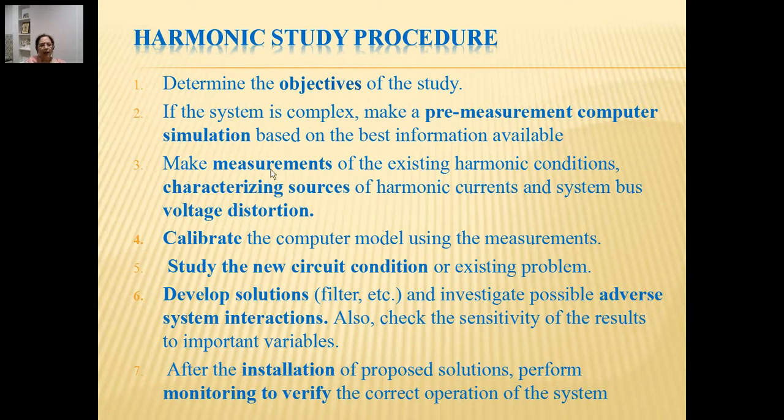because of a particular combination of equipment in a particular industrial setup. Before we go for any measurements for harmonic study, we must decide at what location the harmonics must be measured, and what order of harmonic would be present. The settings and the duration for which it should be studied can all be decided after checking the simulation results. Make measurements of the existing harmonic conditions, characterizing sources of harmonic currents and system bus voltage distortion.